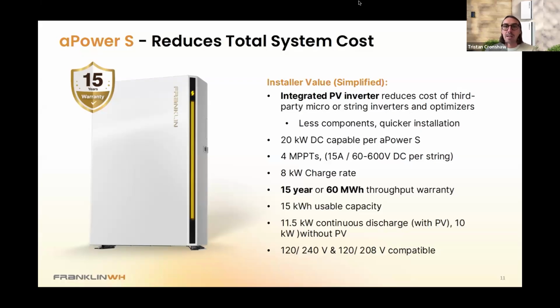But just to highlight, it's an integrated PV inverter, so that's going to reduce any external PV inverter requirement, and you can connect up to 20 kilowatts DC of PV to a single aPower S, right? So that solar can be connected across 4 MPPTs. Each MPPT has a current and voltage range of 15 amps and 60 to 600 volts DC per string. And that's 5 kW DC basically per MPPT.